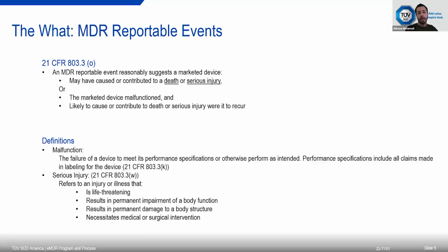The last point that I would mention is that, as I said earlier, submitting a reportable event is not a confession that the manufacturer or their employees is responsible and caused the harm. Of course, that's a separate process, procedure, there's investigation if it goes there, but this reporting is first mandatory, and second, it doesn't necessarily mean you're saying that I'm responsible for this event. Yeah, I definitely think that's an important thing for us to remember and really appreciate those key takeaways.